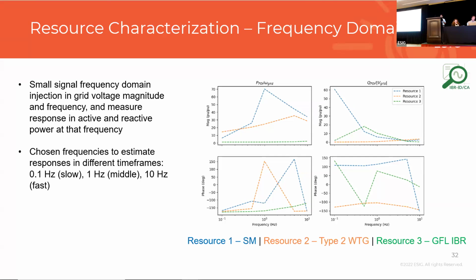If you see an oscillation on the network that's slow, let's take, for example, an inter-area mode, which is extremely slow moving, 0.1 hertz, 0.2 hertz. The idea is that that falls on the slow response type that we want to characterize. So that moves onto the left-hand side of the frequency axis. If you see an oscillation that's a faster moving oscillation, 8 hertz, 9 hertz, that characterizes on the right-hand side of the frequency graph.